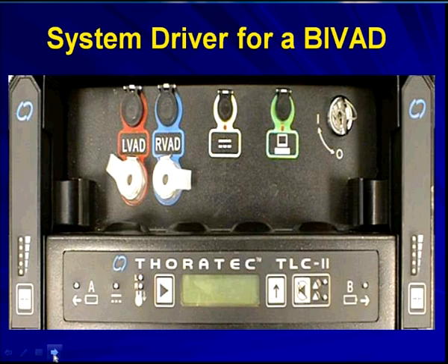You would disconnect the hoses that went into the LVAD and the RVAD, and you would connect these blue bulbs that would be laying next to them, and you would actually take over the left ventricle and the right ventricle by squeezing these blue bulbs and pushing air in and out of the drive line that would keep that BiVAD working and keeping the chambers moving so blood clots don't form.